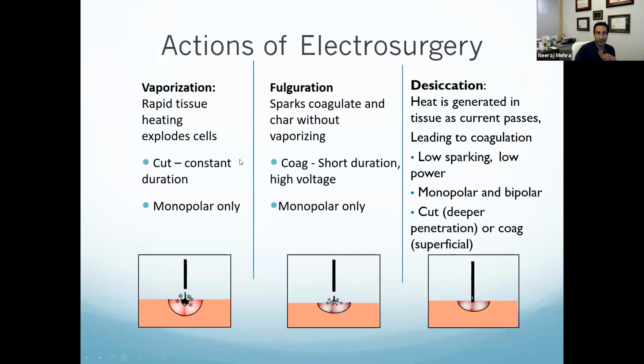So this is our electrosurgery energy. We have vaporization, the cut mode, which only works in monopolar, with constant duration, so it vaporizes the tissue. Fulguration creates sparks, with short duration and high voltage. And desiccation is energy passing through over time. Depending on what mode you use, you'll get either deeper penetration or more superficial penetration. Vaporization, fulguration, desiccation.